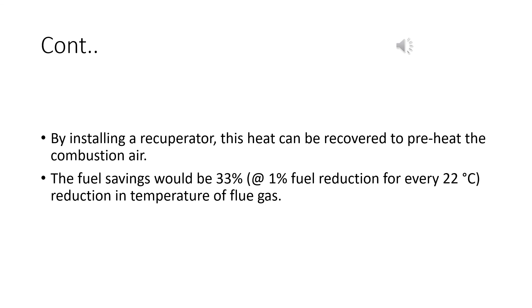By installing recuperators, this heat can be recovered to preheat combustion air. The fuel savings would be 33%, that is, 1% fuel reduction for every 22 degree Celsius reduction in temperature of the exhaust gas.